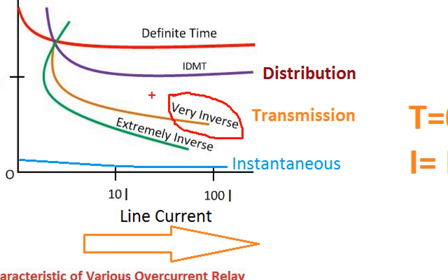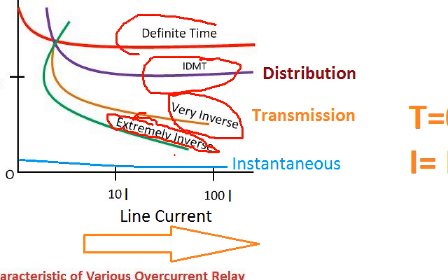We will look at the very inverse type. In the very inverse, the operating time decreases more steeply with increasing current. We will also use extreme inverse — if you have an earth fault on a distribution line, extreme inverse is used for heavy faults. If it is a very inverse, that is the concept.